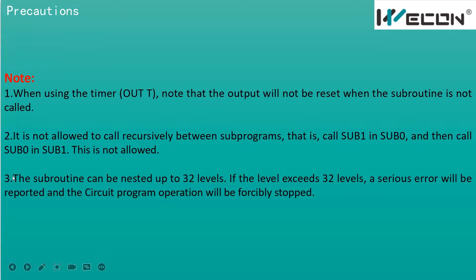The third point: subroutines can be nested up to 32 levels. This means we can call sub1 inside sub0, call sub2 inside sub1, and so on, up to a maximum of 32 levels. If the nesting level exceeds 32, the PLC will also report an error.